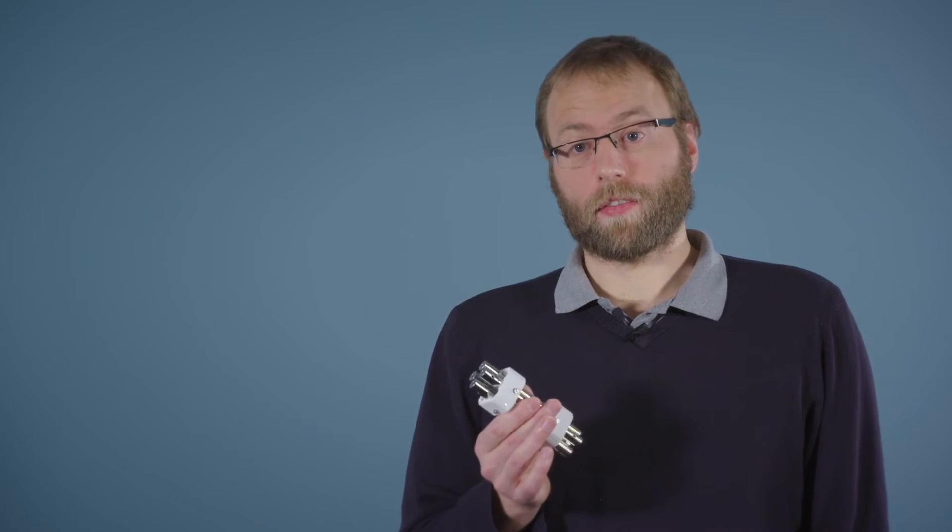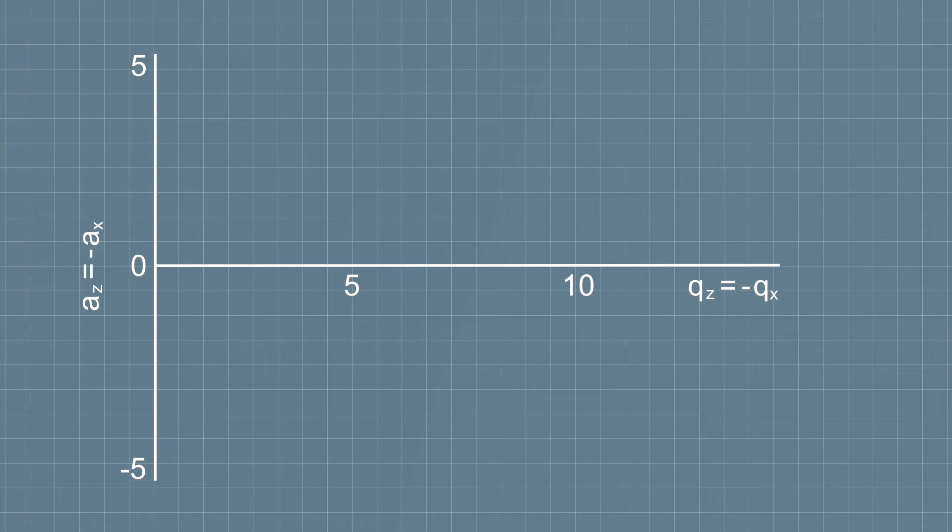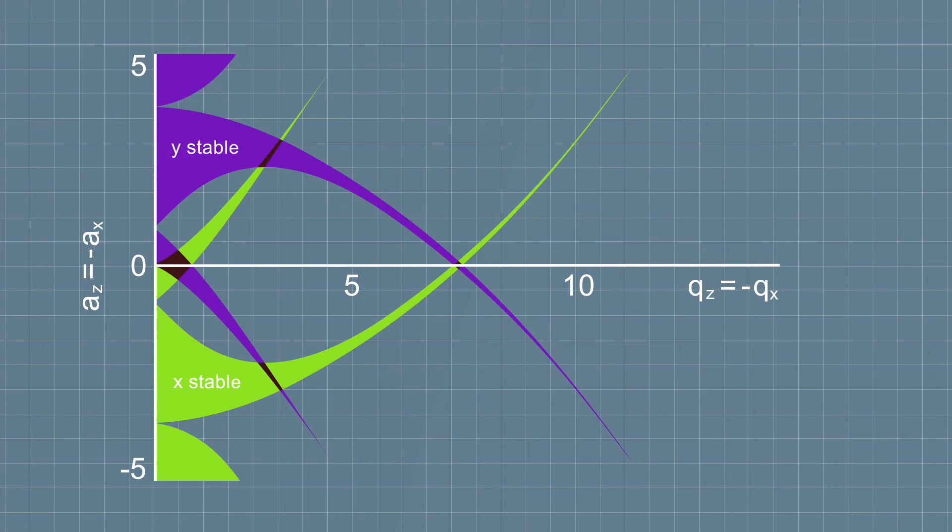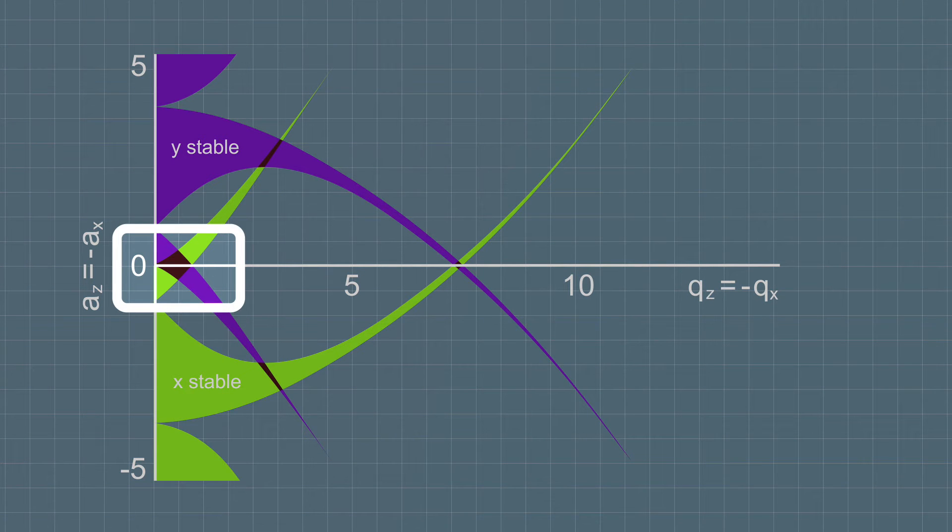So plotting this gives the following. Obviously, for an ion to make it through the quadrupole, it needs to be stable in both the X and Y axis. And from this plot, we can see that there are several regions where the stability zones overlap. But all commercial quadrupoles use what's called the first stability region, mainly because this is where the voltage requirements are the lowest.